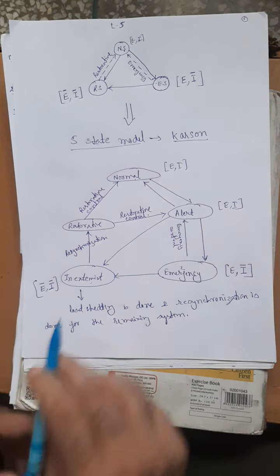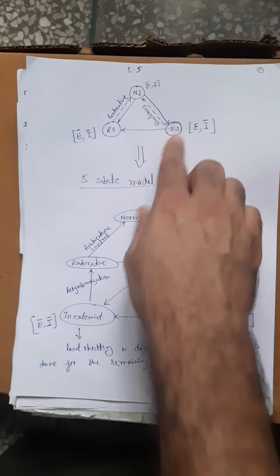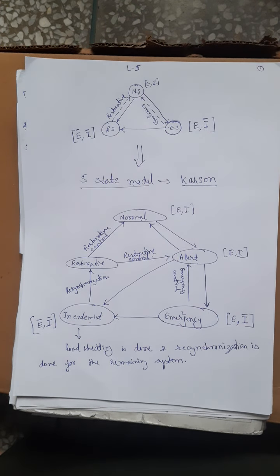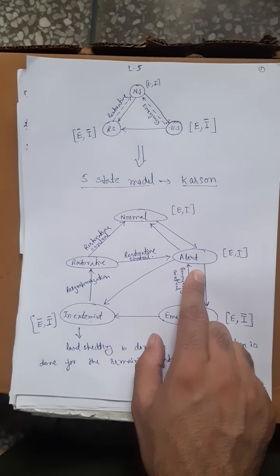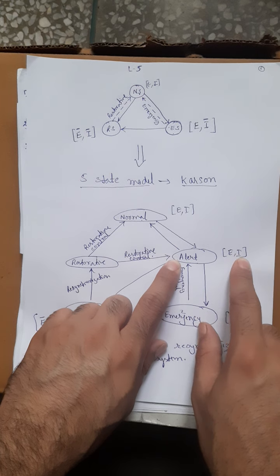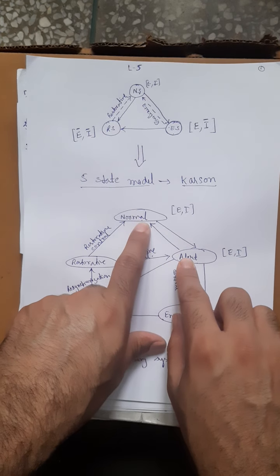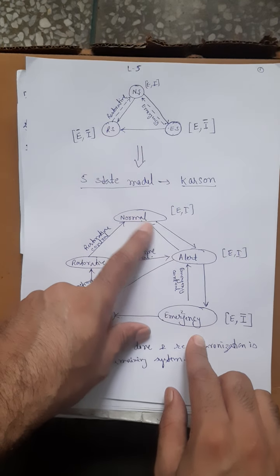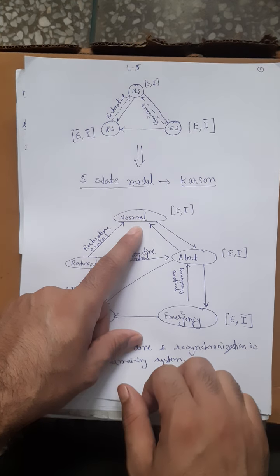The key difference between the three-state and five-state models is that in the three-state model, there is no warning to the operator before the system enters the emergency state. In the five-state model, the alert state gives the operator a warning that inequality constraints are about to violate, allowing corrective action to be taken.